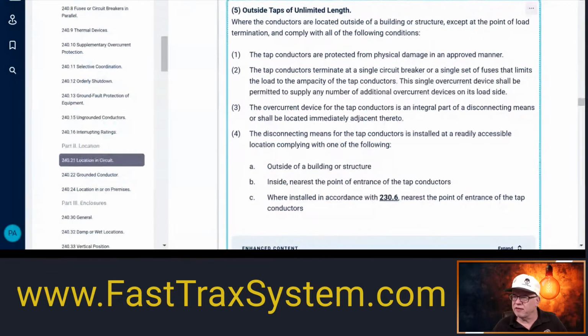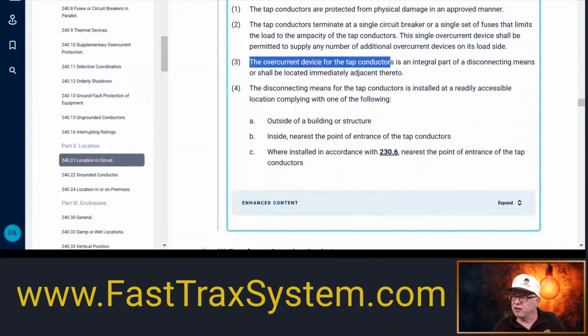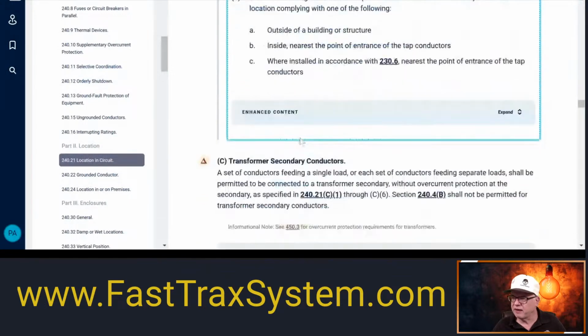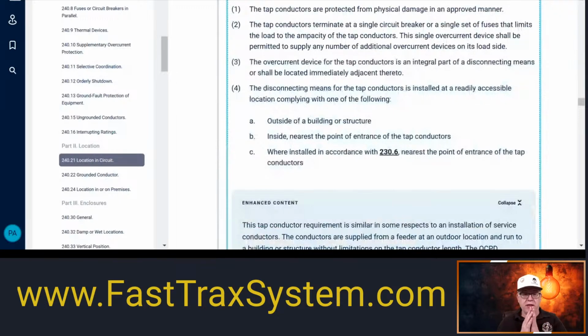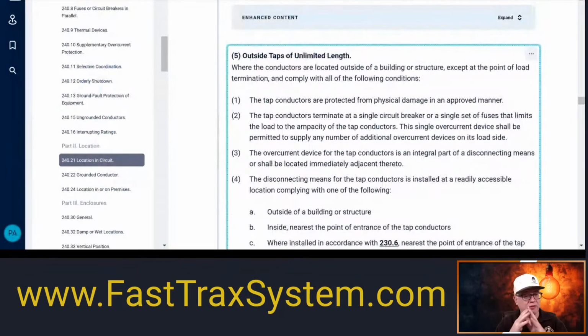All right. Next is the overcurrent device for the tap conductors is an integral part of a disconnecting means or shall be located immediately adjacent to. Okay, so let's see if we have an illustration. Again, if you have a panel with just breakers in it and the disconnect's right beside it, that's fine. Not a problem. Located immediately adjacent means right next to it, immediately. So if the room is there, the space is there, you can't just choose to put the disconnect down the way. If there's room to put it, then it needs to be immediately adjacent to the additional overcurrent devices. So that would be like your disconnect. If you want a separate disconnect and then a main lug panel next to it with all the breakers in it, that's fine. You just can't put the one disconnect, that those taps terminate into, way away.